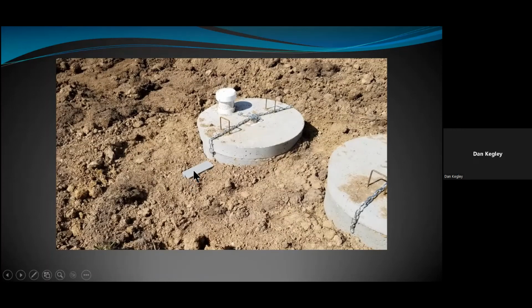So the LB body is not designed to be stepped on. If somebody was to come over there and step on it, by code, it's supposed to be protected from physical damage. So you'd have to put some kind of barriers around it. And you'd probably have to use Schedule 80 versus Schedule 40. So there's all kinds of different things in the codes that restrict the use of a PVC LB, or even a metal LB for that matter.